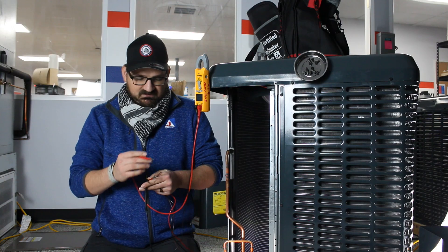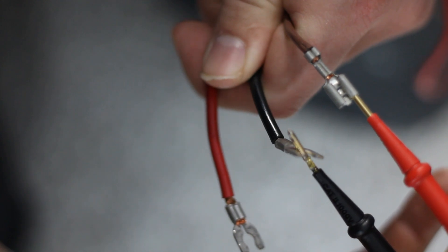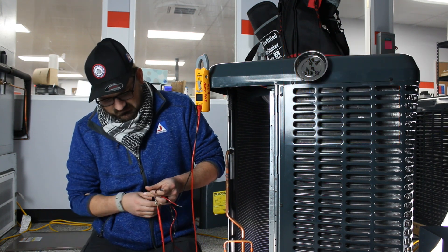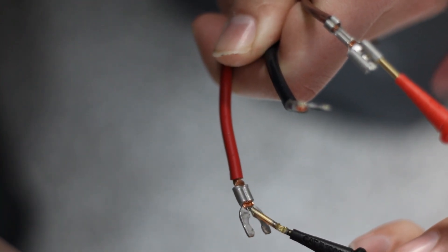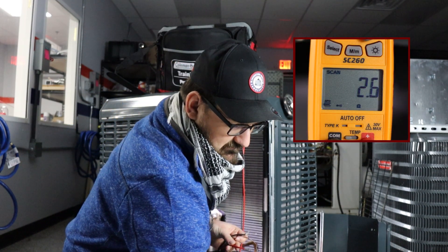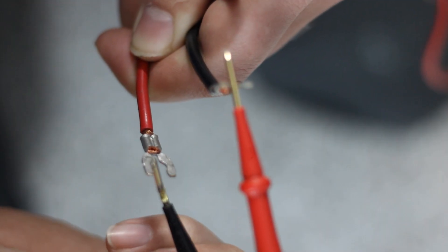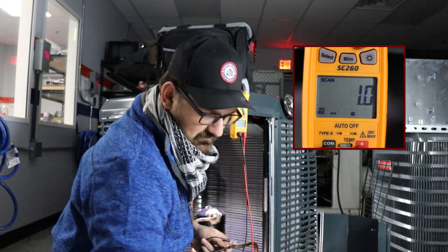So to start, we'll take our meter, set it to ohms, and I'm going to measure between my brown wire and my black wire. We're going to get a resistance reading of 2.6. Then I'll measure between brown and red, and get a reading of 2.6, and lastly we'll measure between red and black and get a reading of 1.0. I'll get that put down as well.